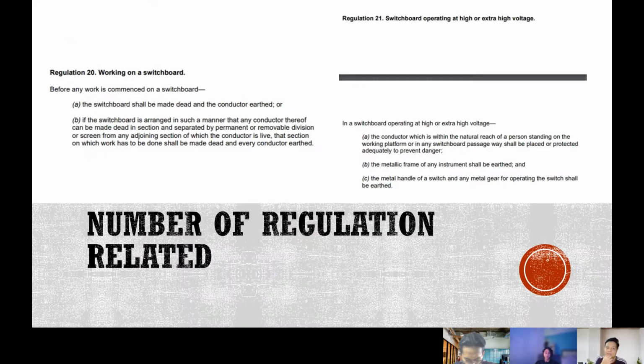Okay, for Regulation 20, working on a switchboard, they explain how to set up the switchboard. Number 1A, the switchboard shall be made dead and the conductor earthed, or if the switchboard is arranged in such a manner that any conductor thereof can be made dead in sections and separated by permanent or removable division or screen from any adjoining section which is live, that section on which work has to be done shall be made dead and earthed. And lastly, Regulation 21, operating switchboard at high or extra high voltage.